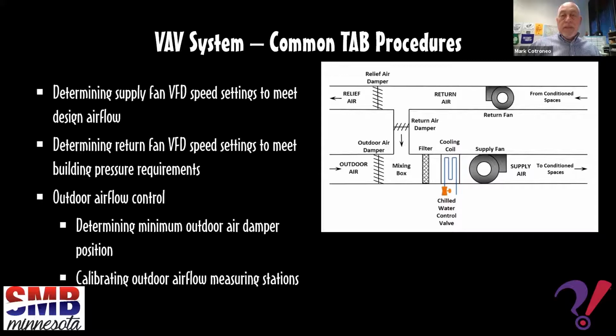Many systems employ an airflow measuring station, usually in the outside air duct, that controls the outside air damper. This needs to be calibrated for site conditions. Similar to the VAV box, a duct traverse is completed and the readings compared with the BAS display. An adjustment factor or gain is then input into the airflow measuring station or the BAS.